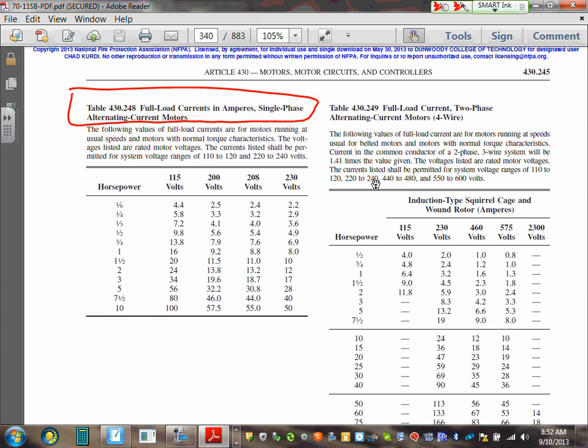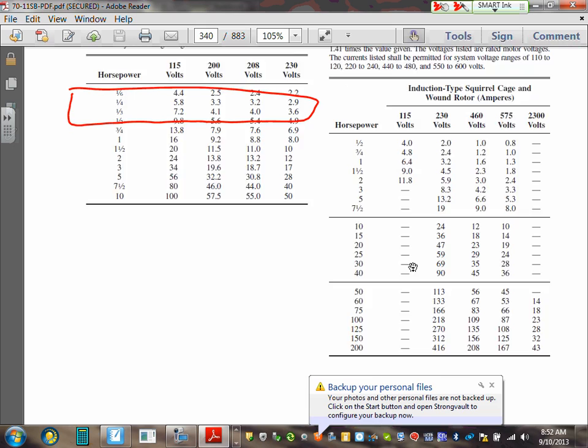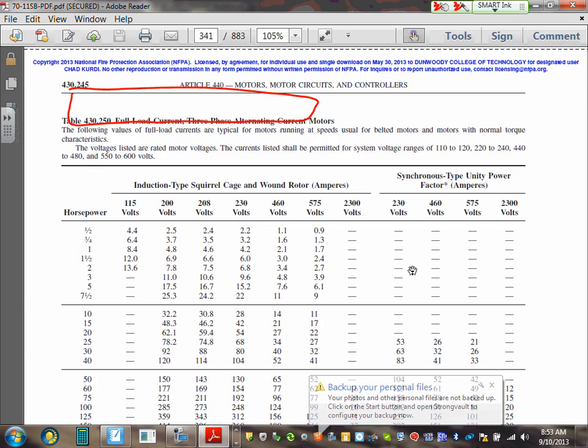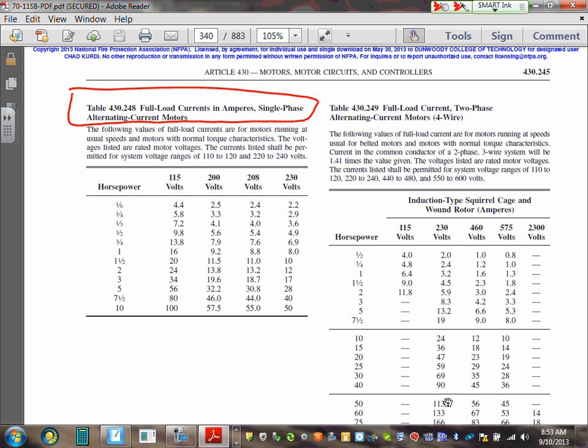Please highlight this table. This is table 430.248. There are many tables. This is for single phase. This is for two phases. And there's one at the bottom, before I go there, they're all the same. This is for the three phase, right? Can you guys see that? So this is how you read this table. This is for single phase, and it goes for ranges of voltages. Can you guys see the ranges of voltages? Right here. If your voltage is between 110 to 120, it covers it. If your voltage is between 220 and 240, it covers it.